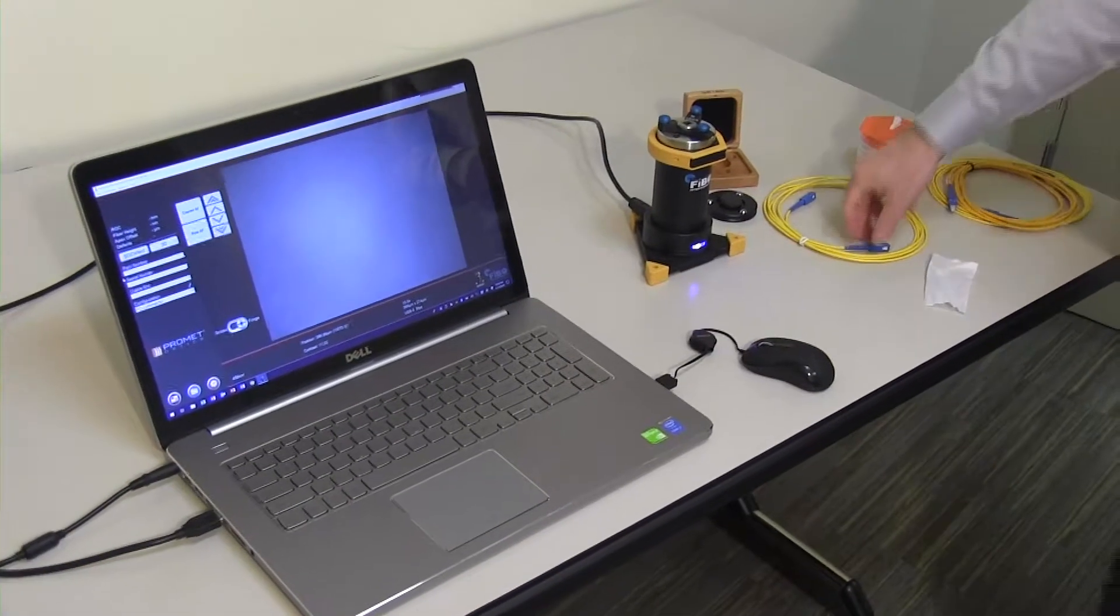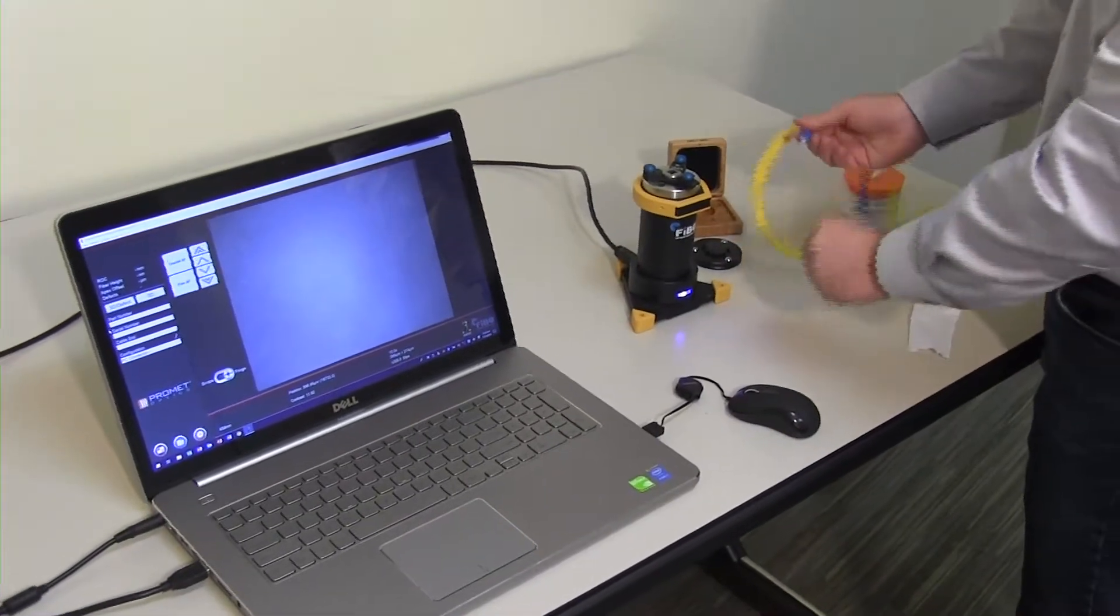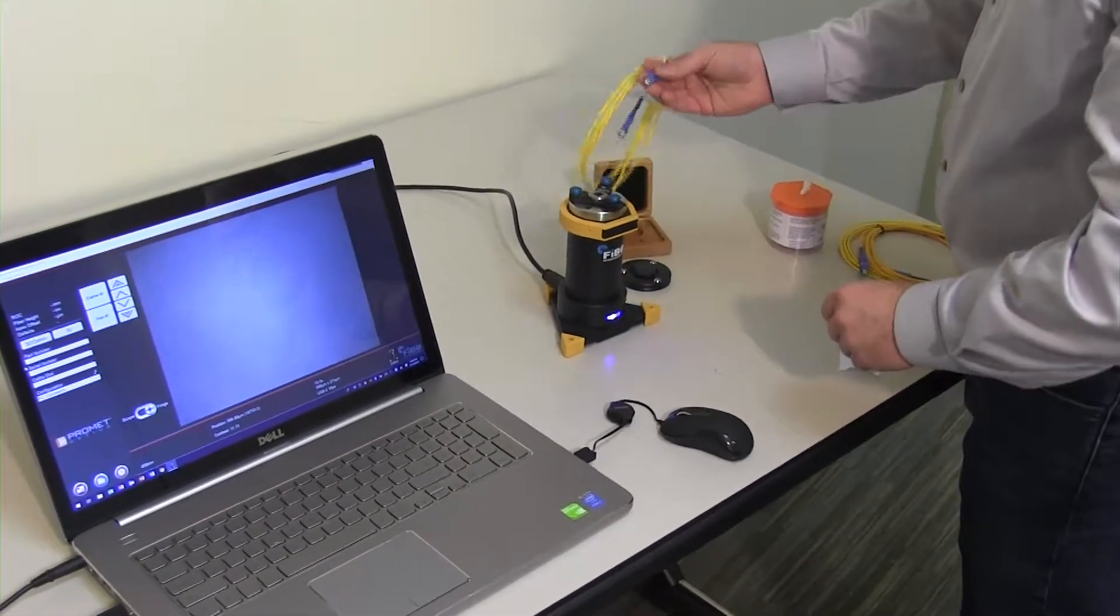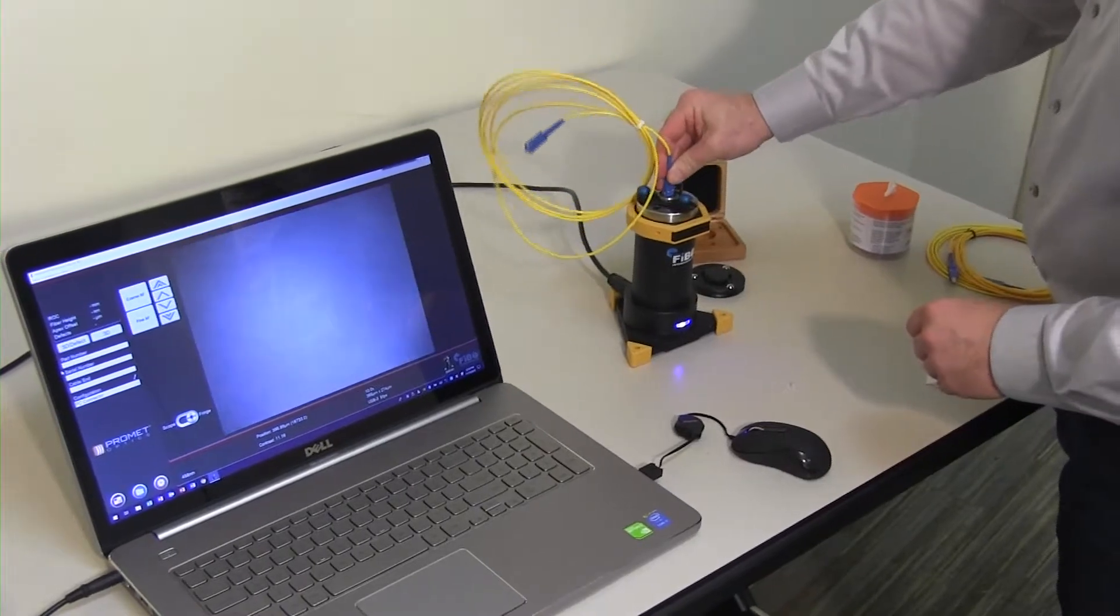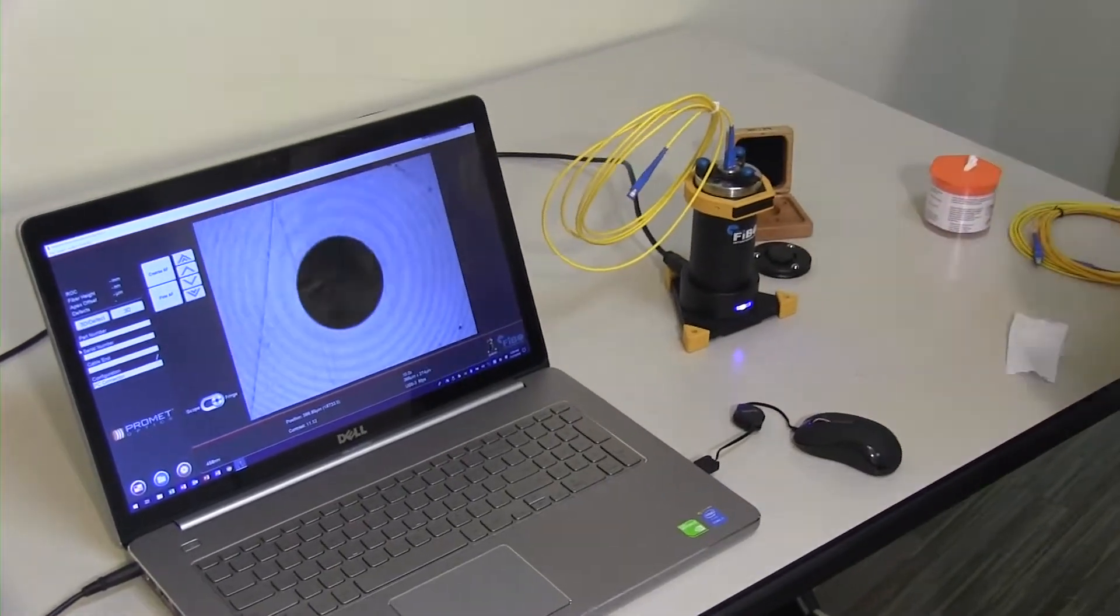The interferometer is the only instrument that can analyze, map, and document the physical surface geometry of a ferrule end-face to determine its suitability for use in a fiber optic system. Any defects are easily discovered, so corrective action can be taken if necessary.